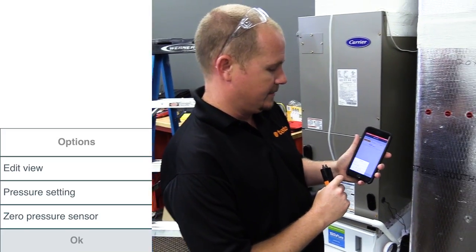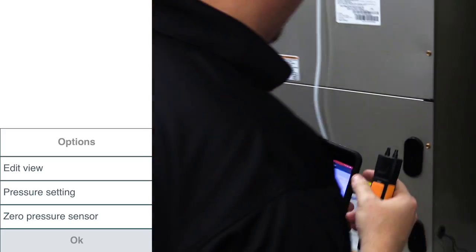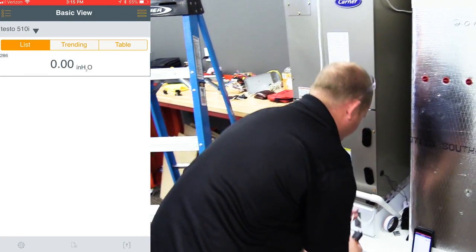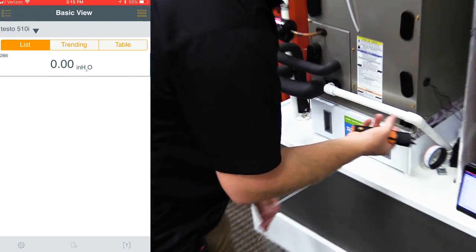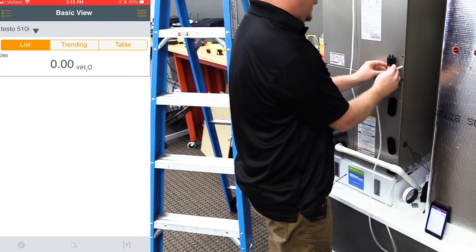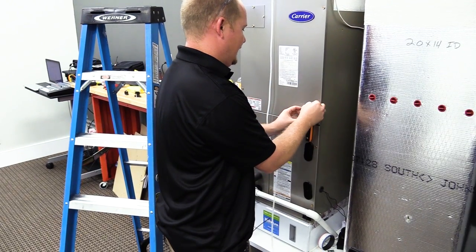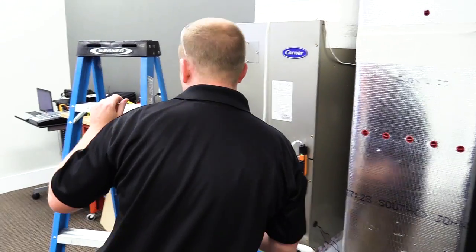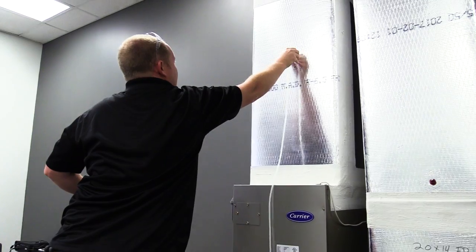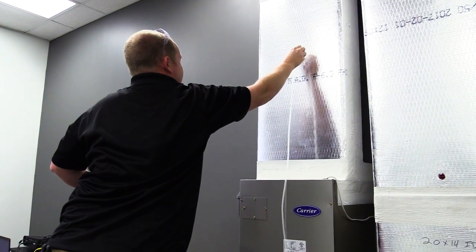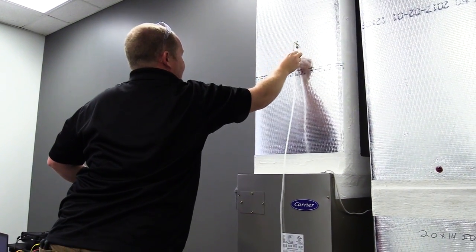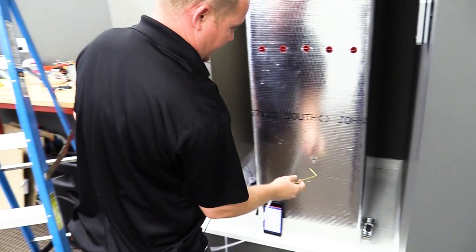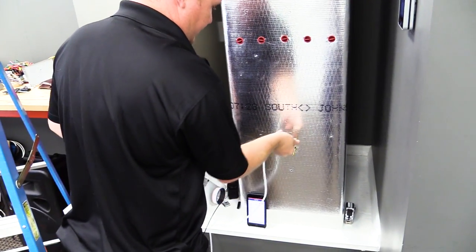First off, we need to zero out the sensor. Now the sensor's zeroed out, and all we're going to do — we have one probe that's already placed on top of the filter, and we're going to place that on the negative side because it has a higher negative pressure, and then we're going to take our probe that was previously in the supply and connect that on the other side of the filter, so that way we can measure the pressure drop.